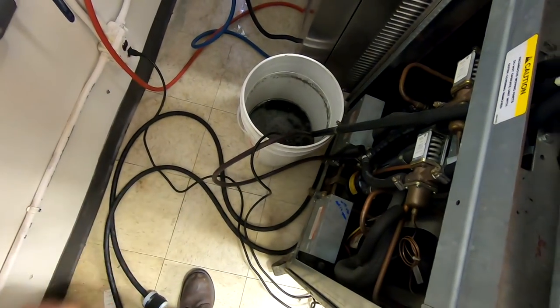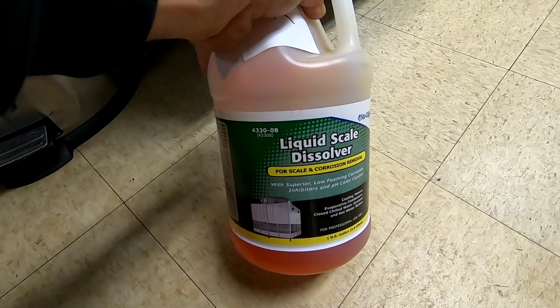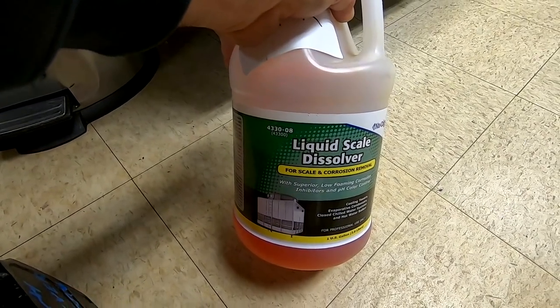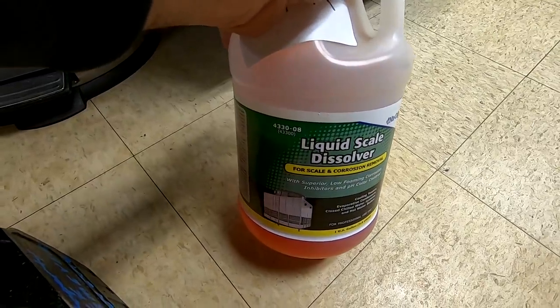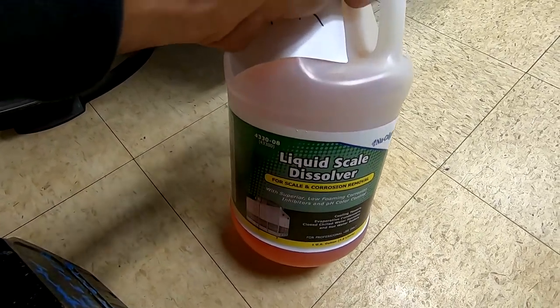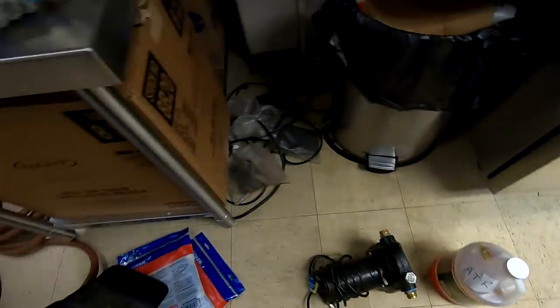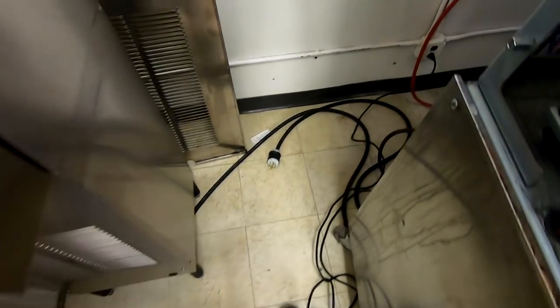Get this rinsed out with water and get all that acid out of there. What we were using on it to dissolve it was some NuCalgon liquid scale dissolver, and the pump we got in there was actually a little pump made by NuCalgon that's all sealed and that's actually made for acid like this.